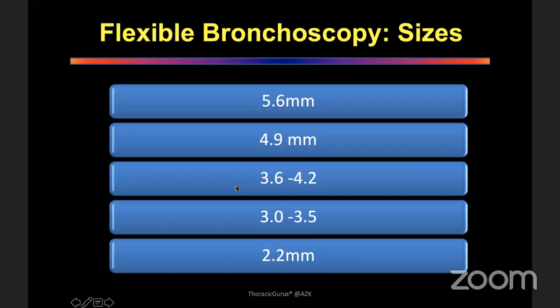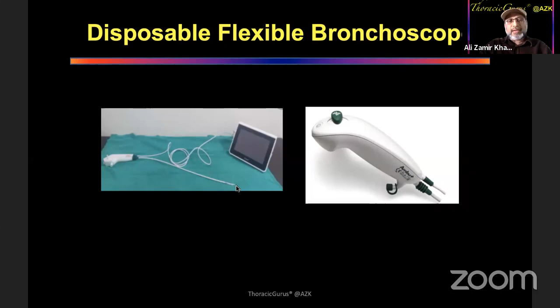As compared to that, this disposable bronchoscope is based on optics rather than fibers. So there is a camera at the tip of that bronchoscope, and that is relaying an image down here. So there are really no fibers running down this bronchoscope. So no matter how much you manipulate it, you cannot snap the fibers. So the image remains constant. And again, with the technological advances, I'm pretty certain that these images will become more and more high definition, and you'll get better picture on the screen. So this is an area where a lot of people are still working on, and I think things are going to change quite dramatically. So this is an EBUS disposable bronchoscope.